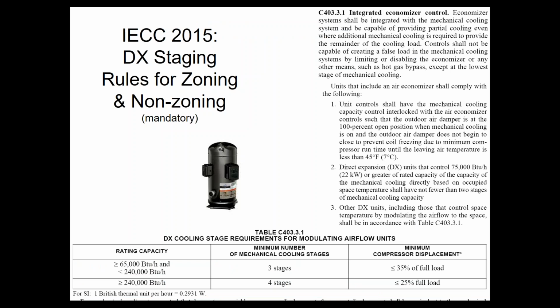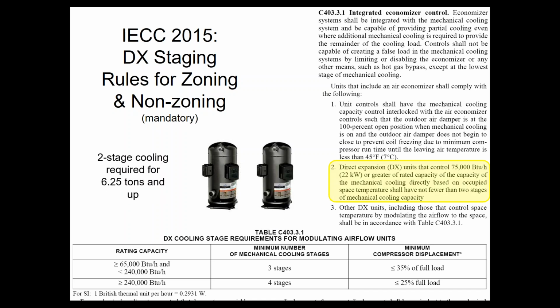Additionally, I showed you this one before, integrated economizer control, but I skipped bullet point 2 and 3. Saved it for now because I don't really feel it belongs in the economizer discussion. It's kind of a separate thing. It relates to economizers, but it's separate. So bullet point number 2, if you have a system that is 75,000 cooling BTUs or higher, which is more than 6 tons, then you must have 2 stages of compression. You cannot have a 1-stage unit. You must have 2 stages or more.